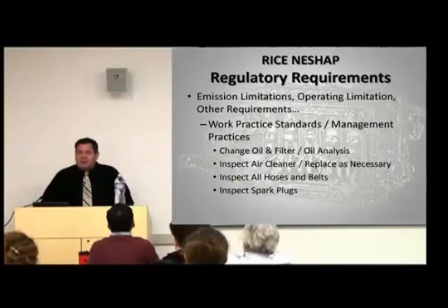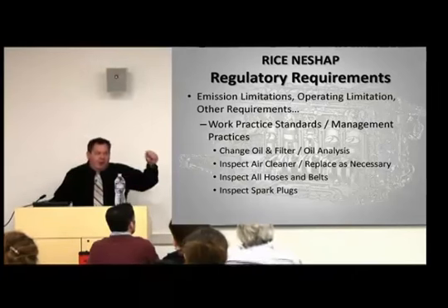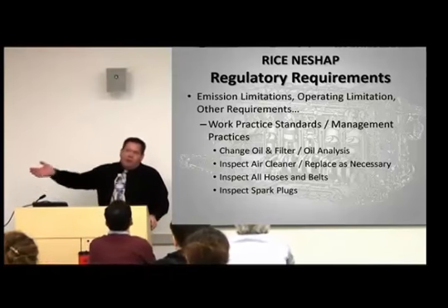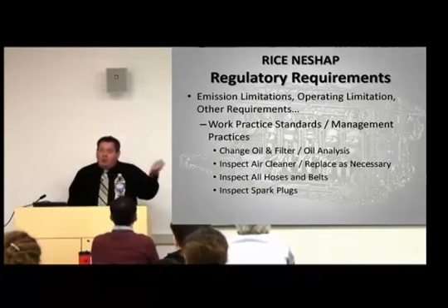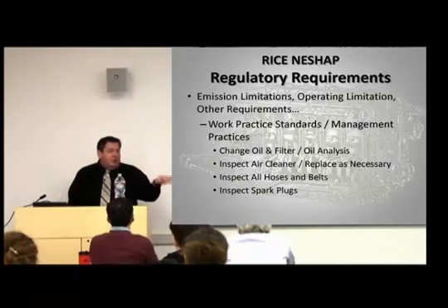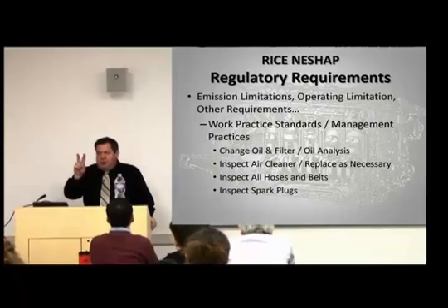Plus, it's totally unnecessary. So they added in an option for oil analysis on the same intervals: 500 hours, 1,000 hours, 1,440 hours, 4,320 hours, the same intervals that you would normally change your oil and filter. You can take a sample out, send it out to an oil analysis lab, and wait for the report to come back. If the report comes back that the oil is in still good serviceable condition, you're good to go until the next interval. If the analysis says your oil is no longer in good serviceable condition according to the specifications and the regulation, then you have to change it within 2 days.